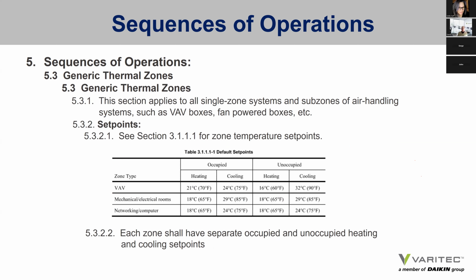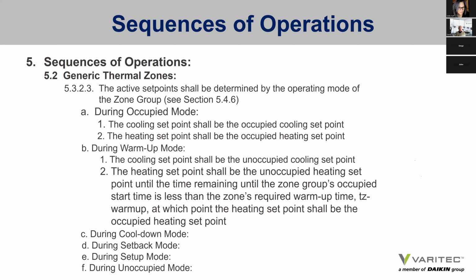zone rooms. There are generic thermal zones, and as the Section 5 goes on to state, the thermal zone in a VAV system is identical to a ventilation zone. The section applies to all single zone systems and subzones of air handling systems, such as VAV boxes and fan-powered boxes, as well as assigned set points for each zone, as we described earlier under the Section 3 section. So each zone shall have separate occupied, unoccupied heating and cooling set points as provided in Section 3 of the guideline. Generic thermal zones will also have assigned operating modes.